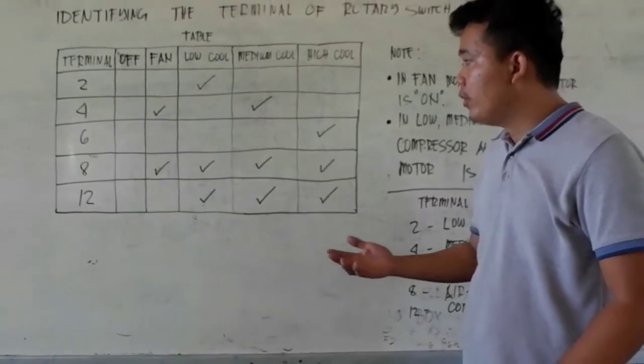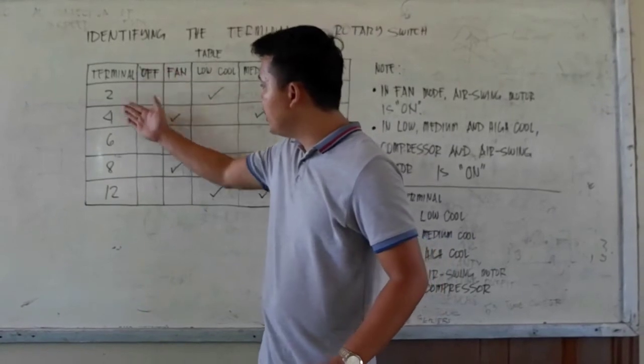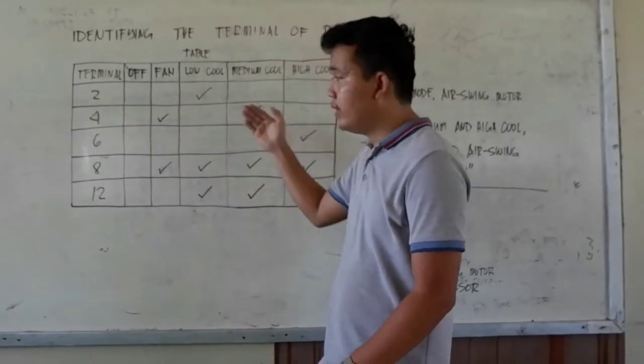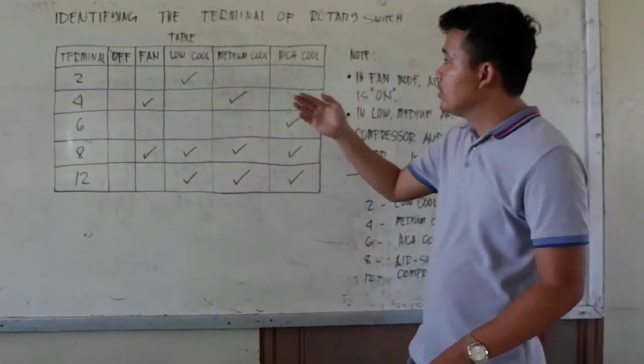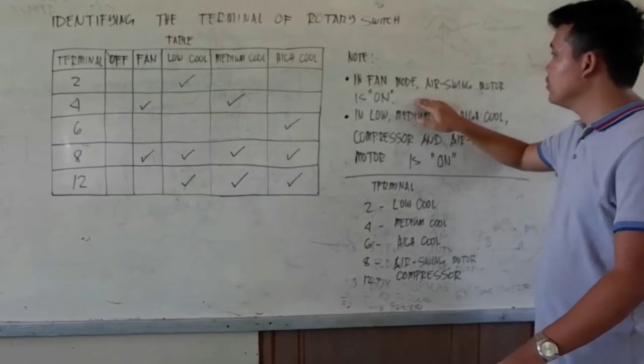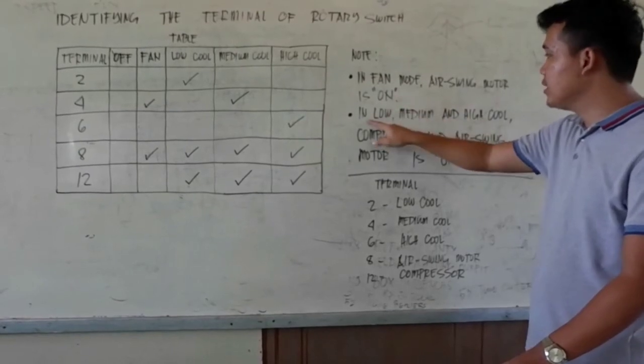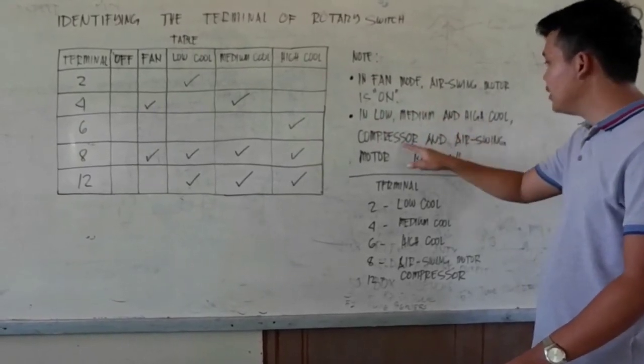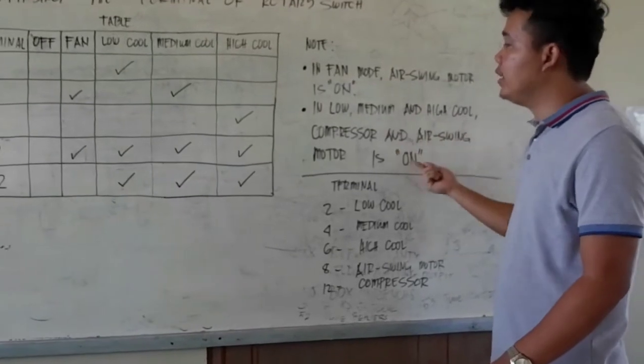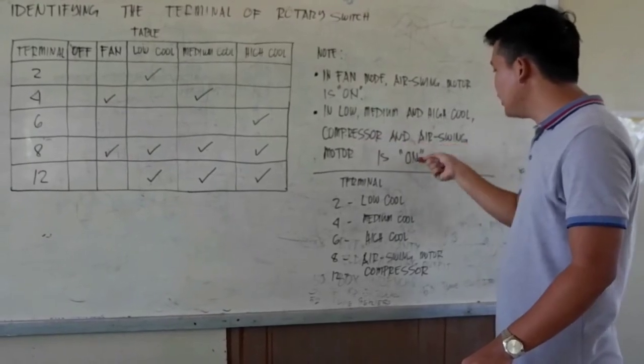Now we are finished testing and identifying the terminals. We are going to find which terminal is the fan, low cool, medium cool, and high cool, based on the records we gathered. Referring to our notes: in fan mode, the air swing motor is on; and in low, medium, and high cool, the compressor and air swing motor are both on. These are our key identifiers.